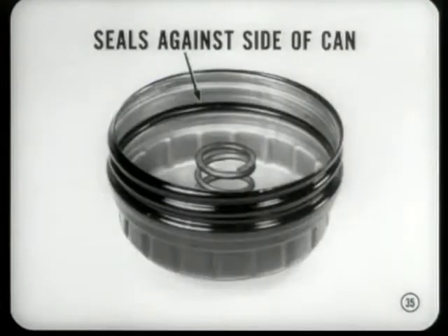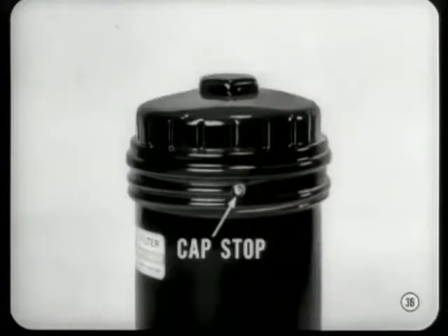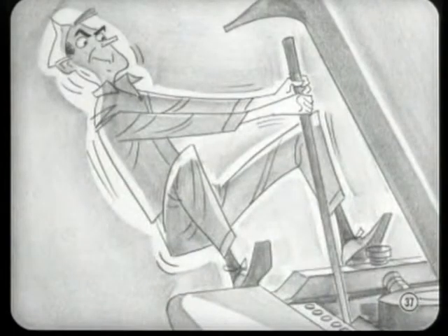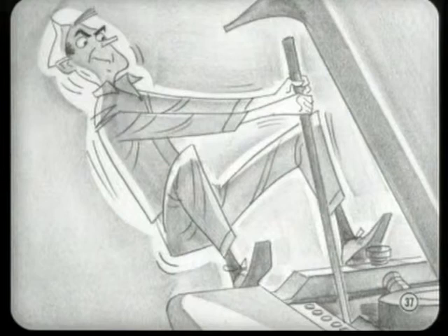Right, Tech. There's an O-ring type seal in the cap of the container. When the cap is turned down, the seal compresses against the side of the can. If the cap is screwed on too far, the seal will be ruined by the threads on the can. Just in case you have big muscles, there's a stop built into the cap and can. When the cap is screwed on the right distance, a hole at the end of the cap threads stops against a bump in the side of the can. If you used a wrench to tighten the cap, you could force it past the stop, ruining the seal and possibly also ruining the cap and can.